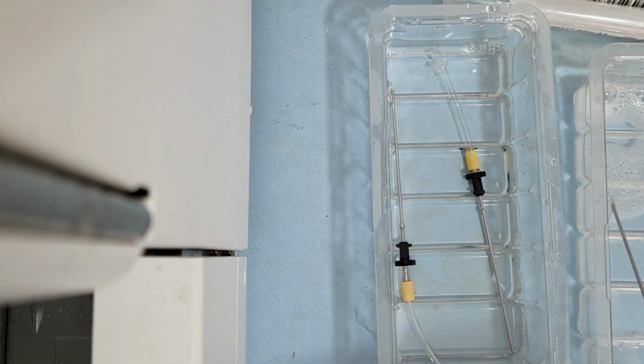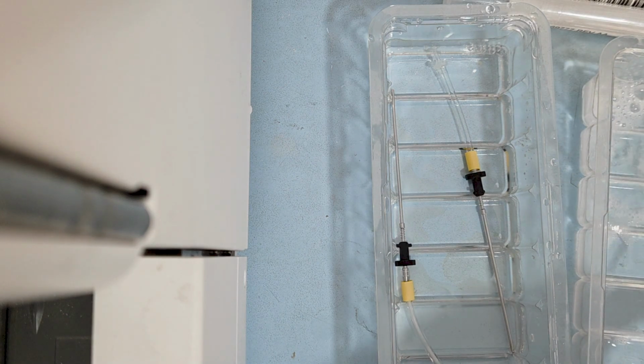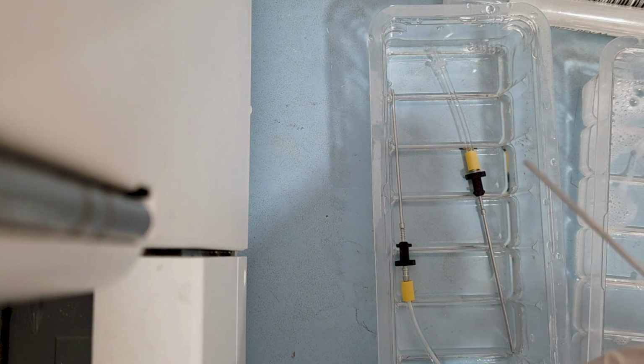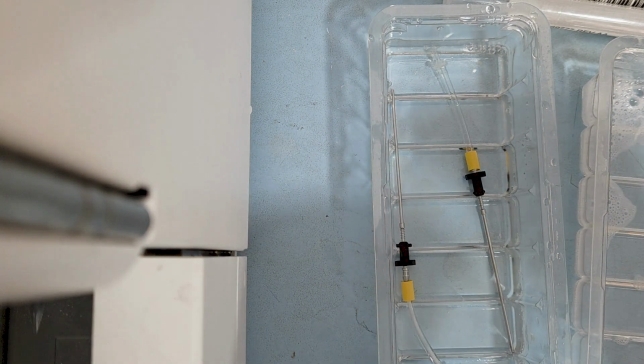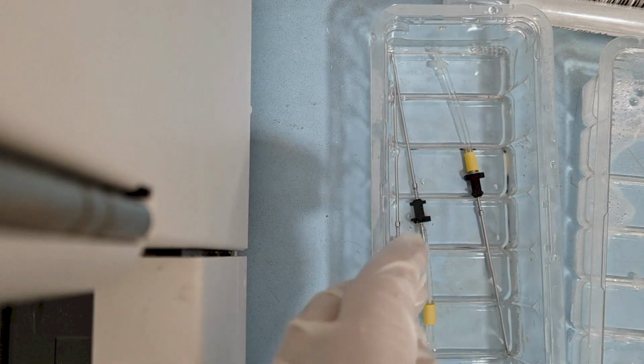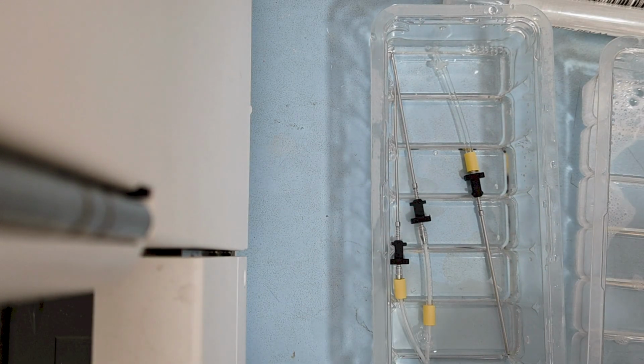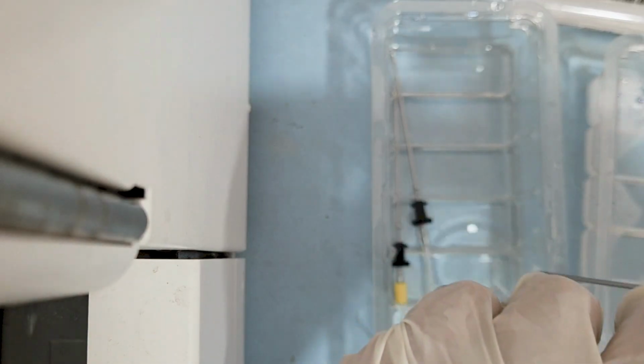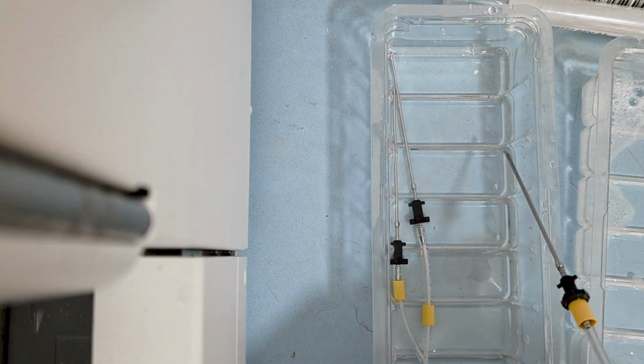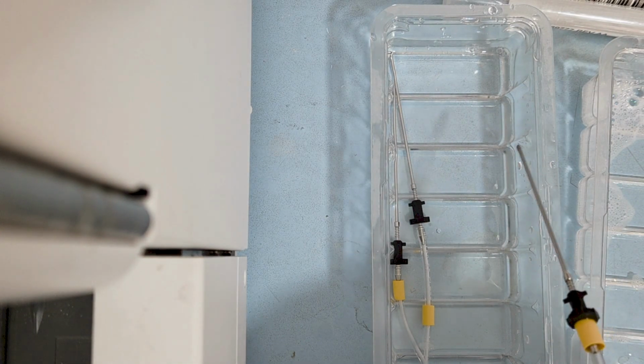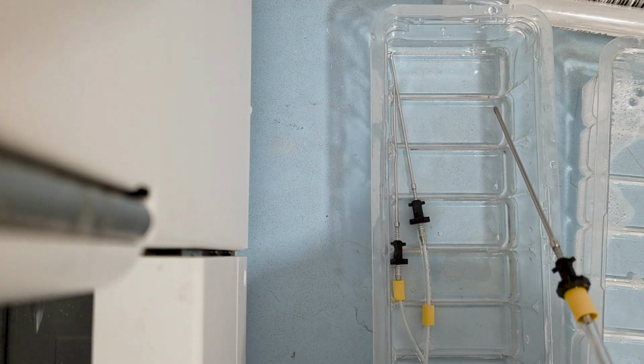And that concludes the procedure for weekly maintenance on the Beckman Access 2 Analyzer, with special emphasis on replacing and cleaning the aspiration probes. So, by following these steps carefully and regularly, we can ensure the analyzer continues to perform with precision, minimizing downtime and maintaining consistent accuracy in our lab results.